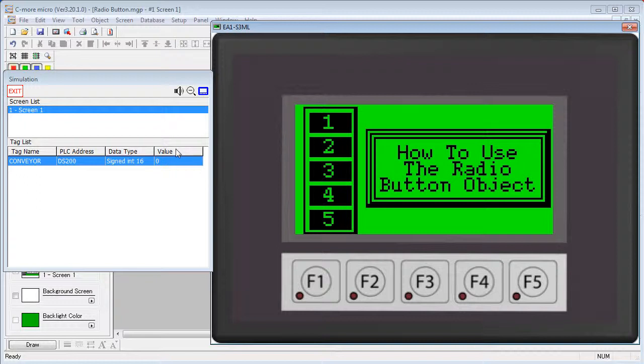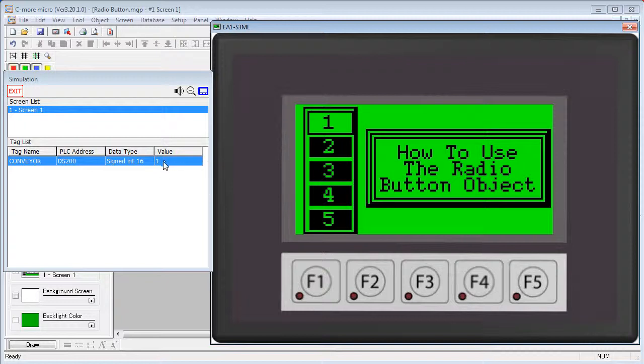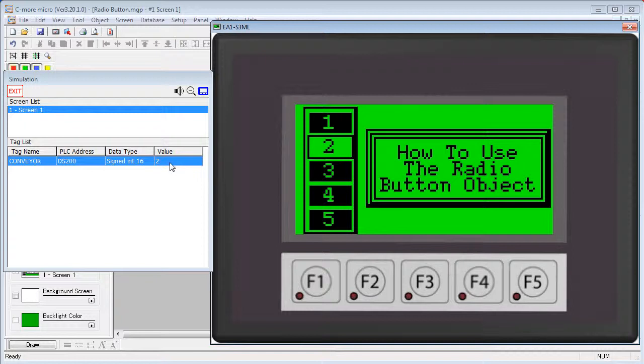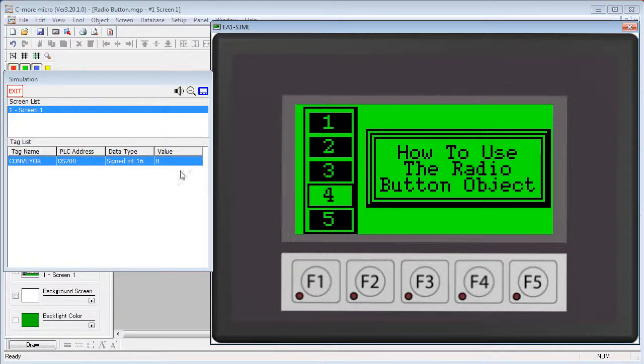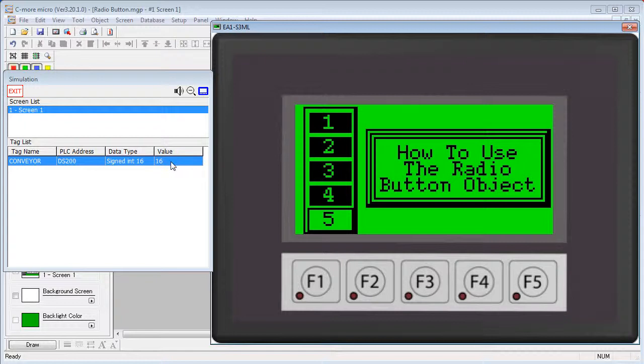Look at how the radio button switch affects the tag. This radio button is connected to this tag. It's a little different than the other switches. The first button changes the tag to a 1, the second to a 2, but the third button changes it to a 4, the fourth to an 8, and the fifth to a 16. See the pattern? Each button on the switch modifies a single bit in a 16-bit word, meaning you are limited to a maximum radio button width of 16 buttons — one for each bit.